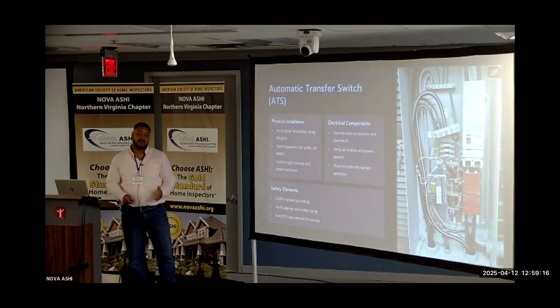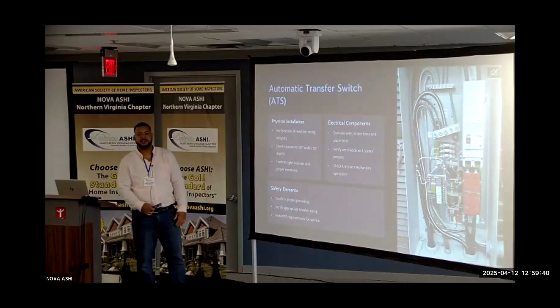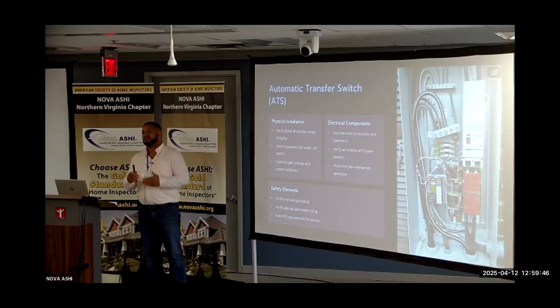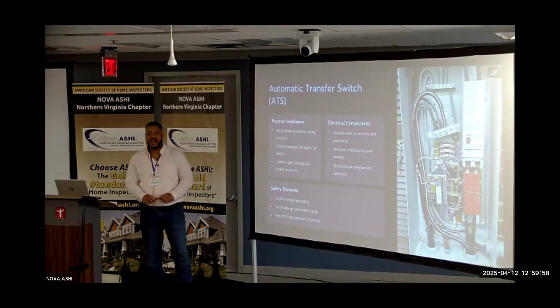You all can make sure that the breaker size is appropriate. You have the 4-aught wire coming in, so you have a 200 amp breaker. How often, when you're in electrical panels, are you looking at the wire size to the breaker size? I'm curious. I know sometimes when we replace electrical panels, I'll take a little snapshot of the existing breakers, and then later we find, oh man, they have the wrong size wire on the breaker, so we have to get the correct breakers.